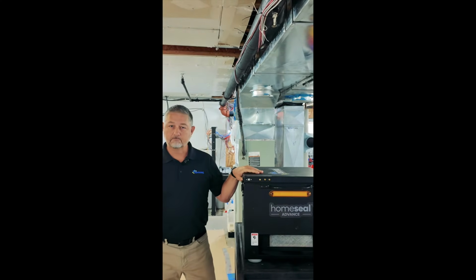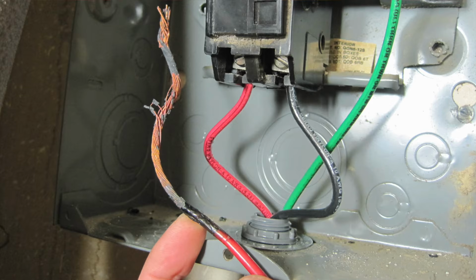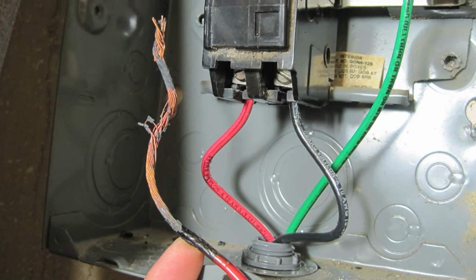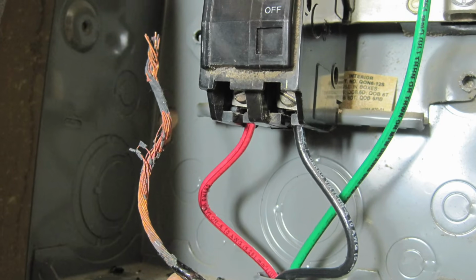Number three, one of the most common issues I see with furnaces. In fact, I can't tell you how many times this one issue caused a plethora of other problems, including misdiagnosis by underskilled technicians, and that is furnaces that have a grounding issue, furnaces that are not grounded properly.